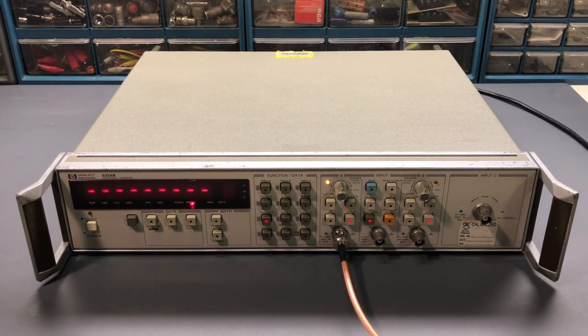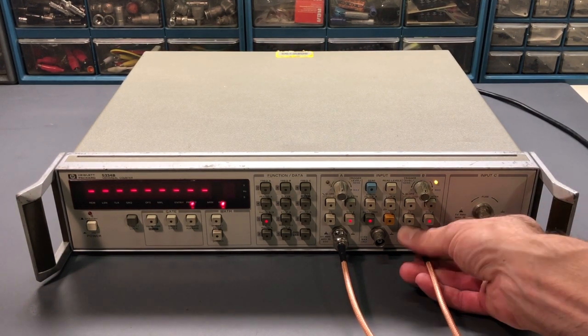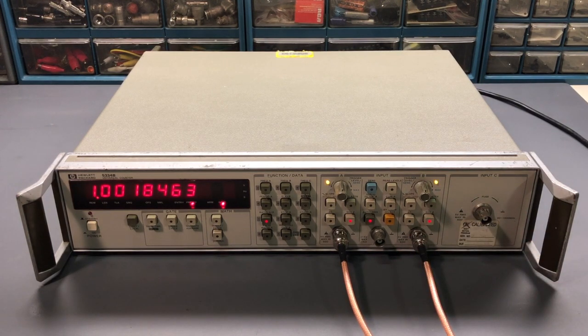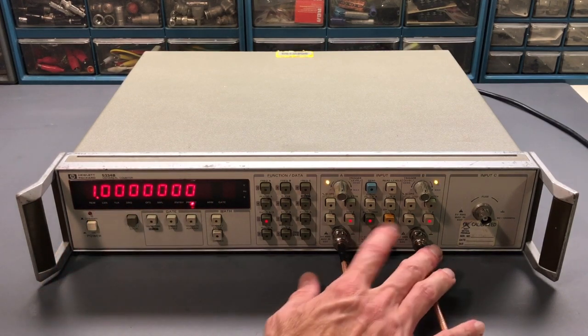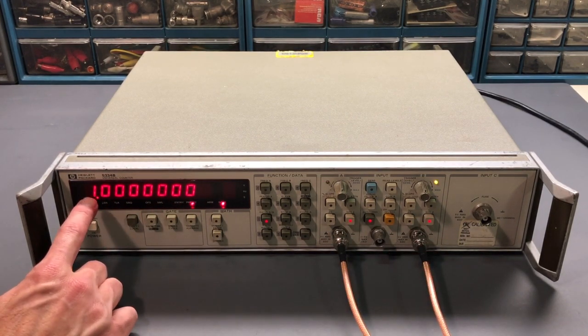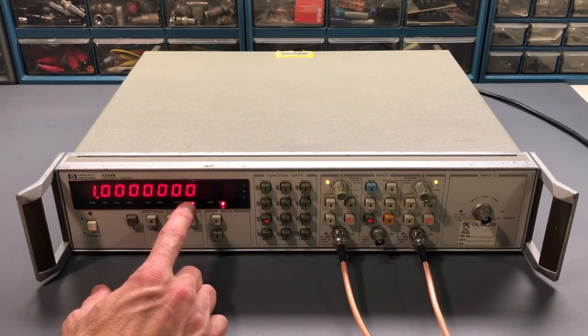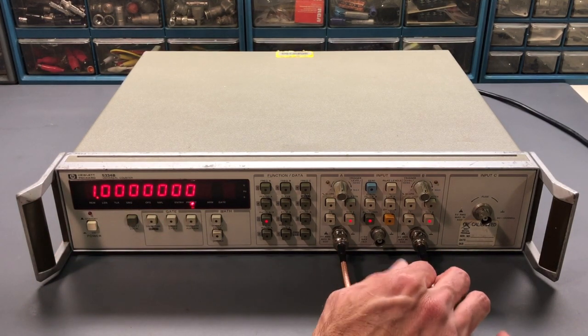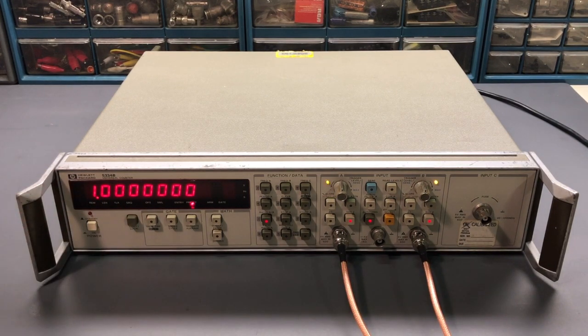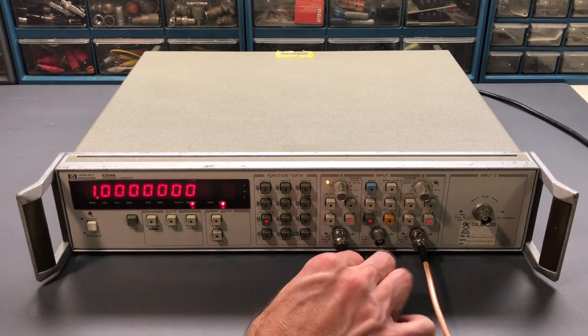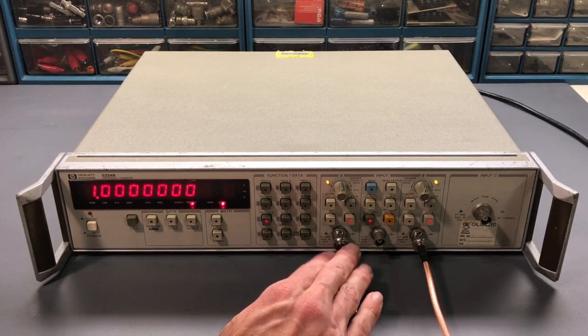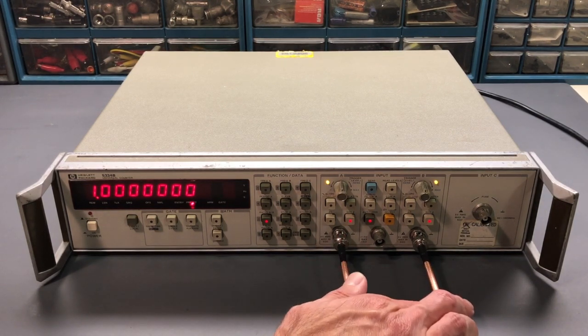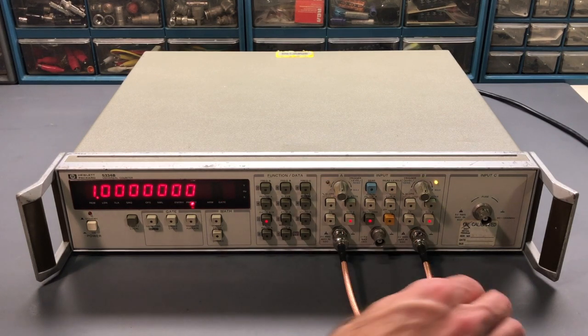Let me grab the other input here. I have a second function generator set to 10 megahertz, and we'll make that connection. So now the ratio measurement between these two inputs reads 1 point and then all zeros, telling us they're precisely the same as far as the instrument can measure. That makes sense, because this is the very accurate GPS-synchronized reference oscillator, and this function generator is also very accurate and set to 10 megahertz.